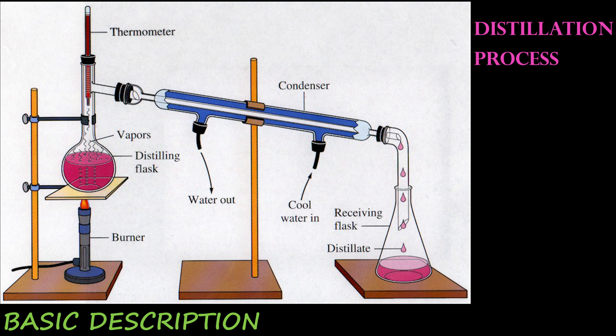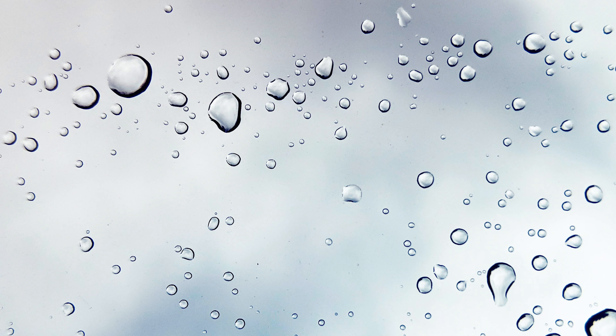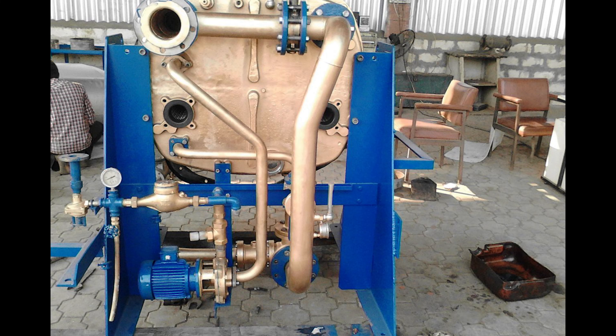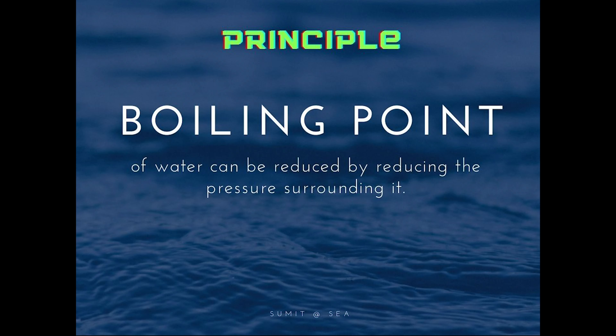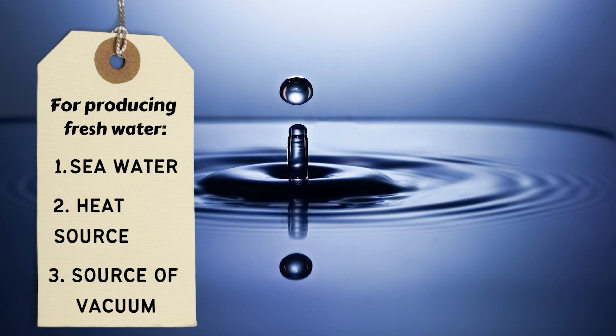What is distillation? Distillation is a process of separating fresh water from seawater by boiling seawater in an evaporator; the evaporated vapors later get condensed in a condenser. There are two types of freshwater generators: number one is plate type, and number two is tube type. The basic principle in all low-pressure fresh water generators is that the boiling point of water can be reduced by reducing the surrounding atmospheric pressure.